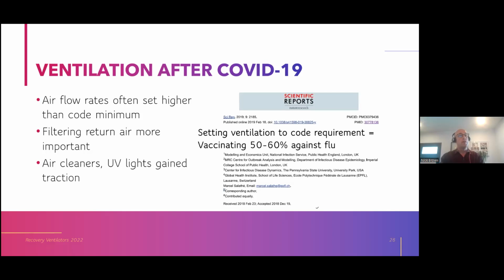Yeah, the best practice is that it's got dedicated ductwork to move the air where you want it. And we'll cover that in a minute. But from an energy code standpoint, the energy code doesn't care how you distribute that air, the supply and the exhaust. It just wants balanced ventilation with heat recovery. So there's a number of options available to you, and we've got a slide coming up on various configurations. So hold that thought, Mike. Thank you.